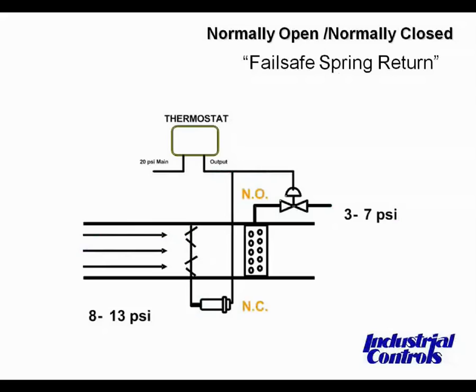Why in each case? The outdoor air damper should fail closed to protect the coil from freezing. The valve on the preheat coil should fail open. This will also protect the coil from freezing and will provide tempered air to the system. Two actuators used on the heating side of the system, yet each require a different safe action.